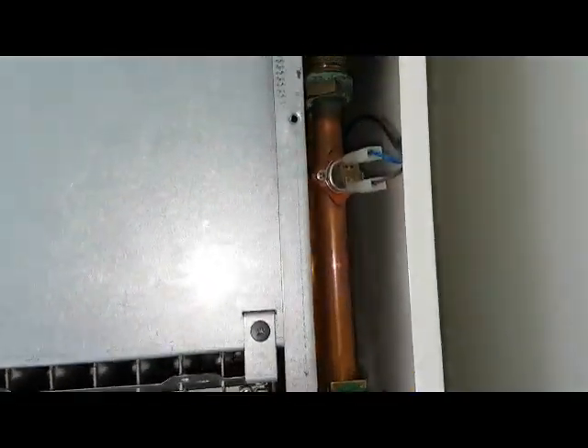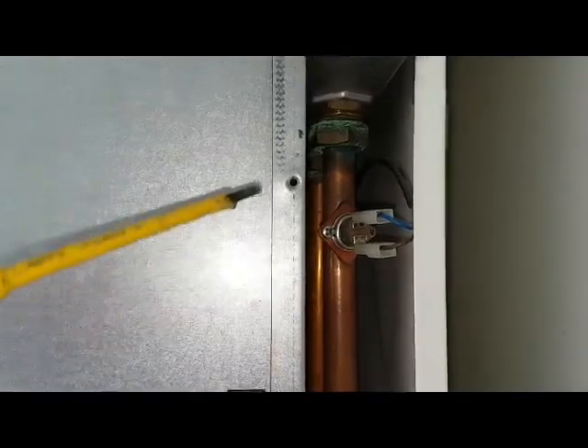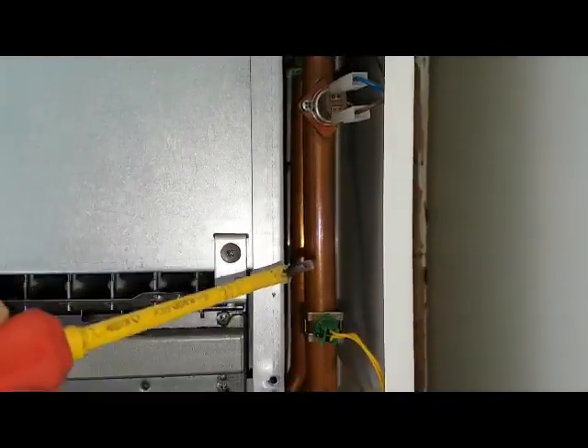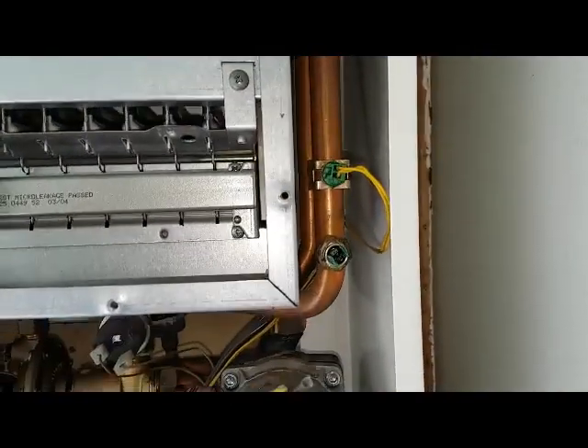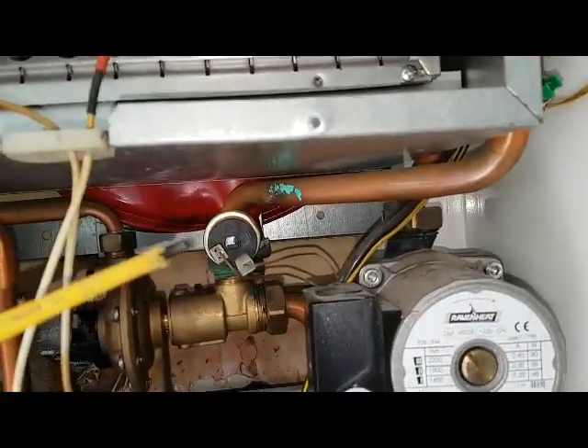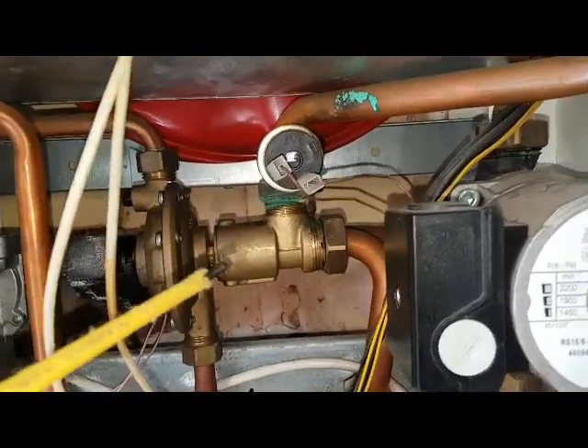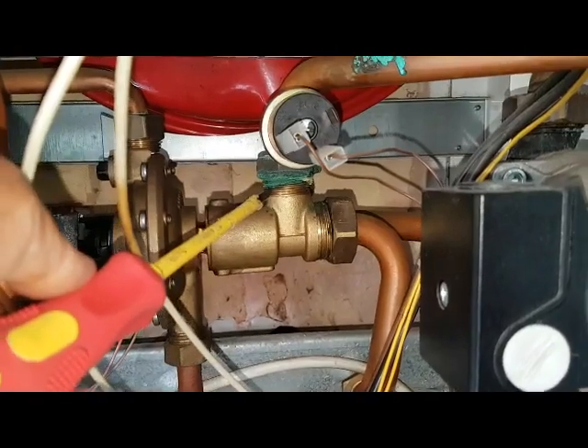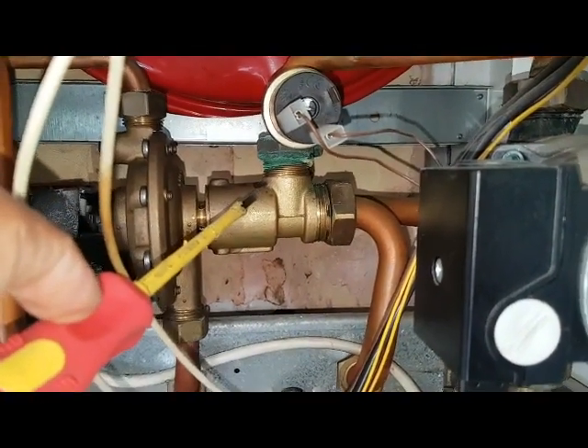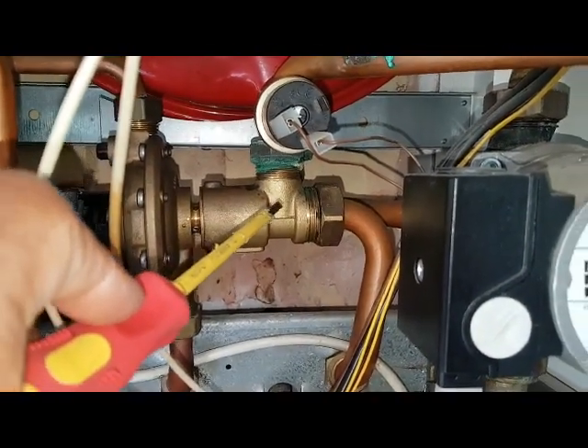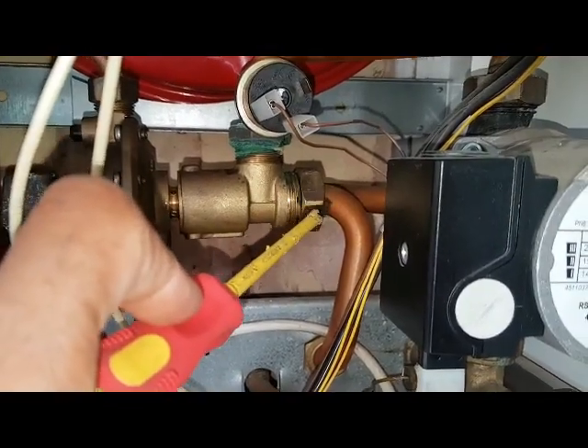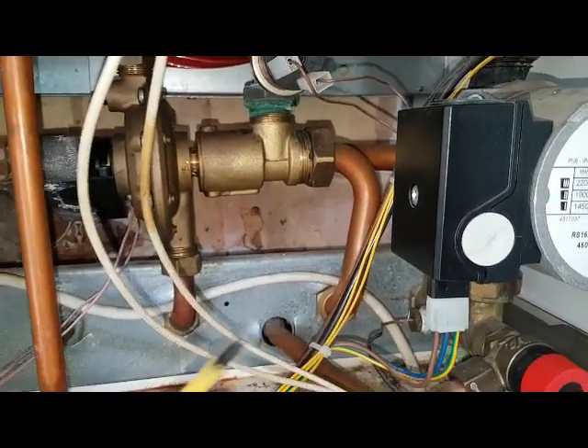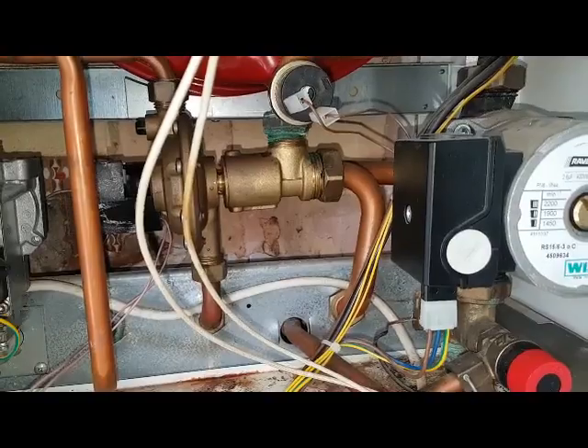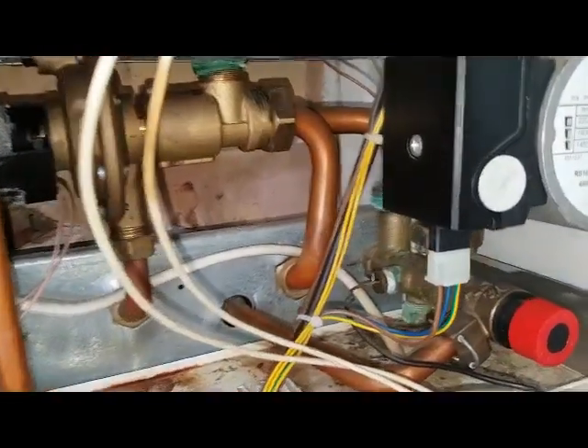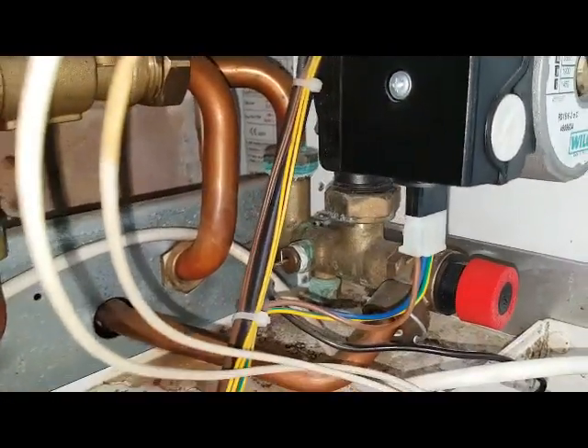So this pipe here is the flow pipe and it's coming down this way. It goes across through the pressure switch. This is a diverter valve. The diverter valve flow goes this way at the end of it and down and out to the radiators. And then it returns back through the pump.